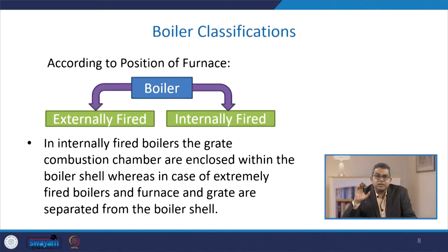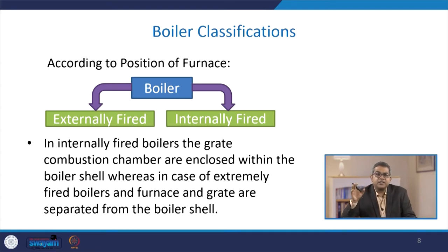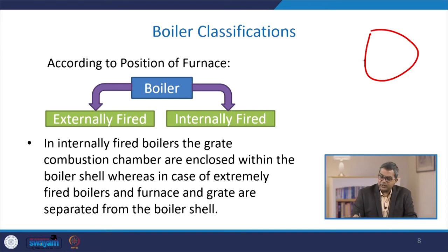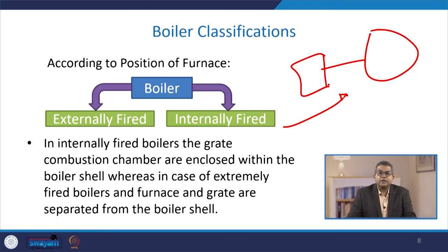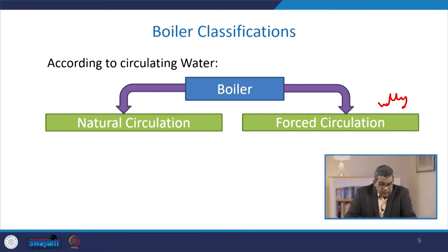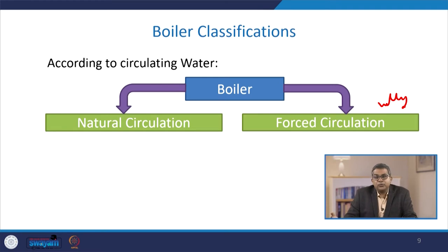Another classification is based on the position of the furnace — either externally or internally. In internally fired boilers, the combustion chamber is enclosed within the boiler shell. In externally fired boilers, the furnace and grates are separated from the boiler shell. Boilers can also be classified based on the circulation of water — natural circulation or forced circulation.